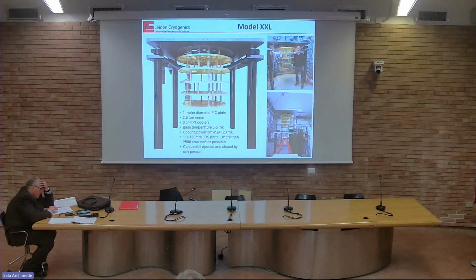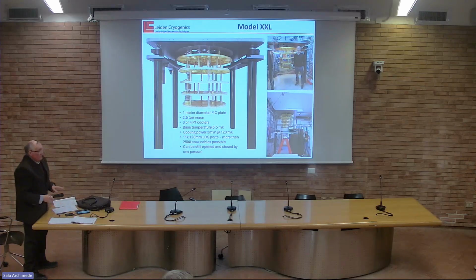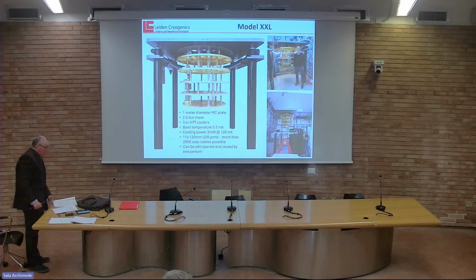Another system that we made and already sold 3 of is a Model XXL. So this cryostat has a mixing chamber of 1 meter, weighs 2.5 tons, and it takes around a week to cool down, but it still reaches a base temperature of 5 millikelvin and a cooling power of 3 milliwatt at 120 millikelvin. It has 120 millimeter line of sight ports. So with high density wiring, you can put literally thousands of lines in it if you need it. And because it's using the same lifting table, it can still be opened and closed by one person.